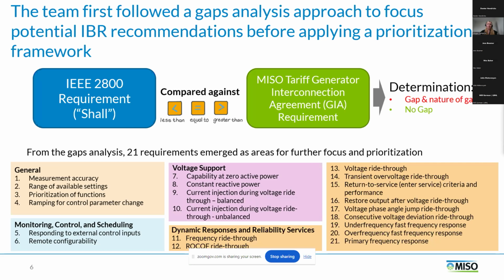We followed a typical gaps analysis approach in comparing the 2800 standard against MISO's generator interconnection agreement language. And the nature of the gaps varied from a requirement being missing in MISO's GIA, partially defined in the GIA, or defined with different parameters, and those were all classified as a gap. So from this analysis, we identified 21 requirements from the standard where there was a gap in our current GIA requirements. And so they fell into the four main categories you can see here: general, monitoring and control, voltage support, and then dynamic response and reliability services. That category encompasses all of the ride-through requirements in 2800.